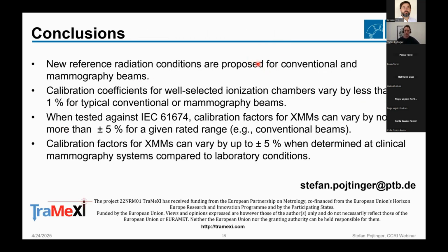What I've shown you today is that we are going to propose new reference radiation conditions. You saw the new copper radiation conditions for conventional and also our idea for mammography. You've seen that the calibration coefficients for well-selected ionization chambers that are typically used as secondary standards vary by less than 1% for typical conventional mammography beams. I've also shown that when an XMM was tested against IEC 61674, the response dependence on energy changes by only plus minus 5% for a given rated range. You have to be sure that you stay within the rated range.